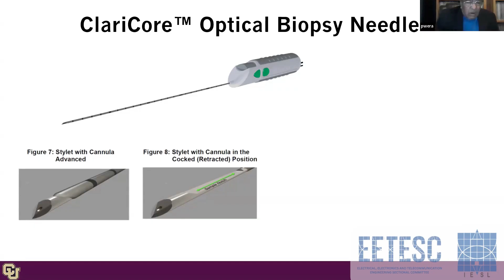And so you excite the tissue. Let us say you turn on the 280 nanometer LED and then read that back. Then you turn on the 340 nanometer LED, read back, and then you have a broadband light source from 400 to 800, and take the signal. All of these, for these three measurements, are done in about 100 milliseconds. That is one measurement. There are 18 measurements we do together.